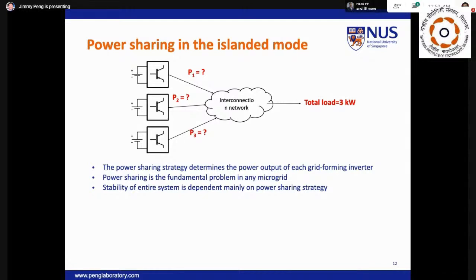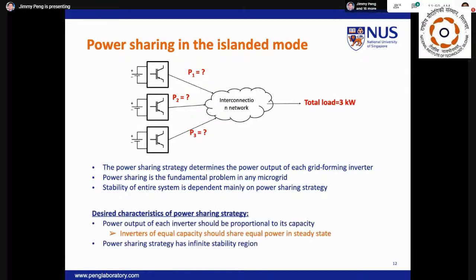For instance, let's look at the 3 inverter case over here. We are sharing a total load of 3 kilowatts. To ensure each inverter is stressed in a similar manner, we will adopt the concept of Droop. Droop ensures each inverter is sharing at a ratio proportional to its capacity. Depending on the power sharing settings, different stability regions are established.